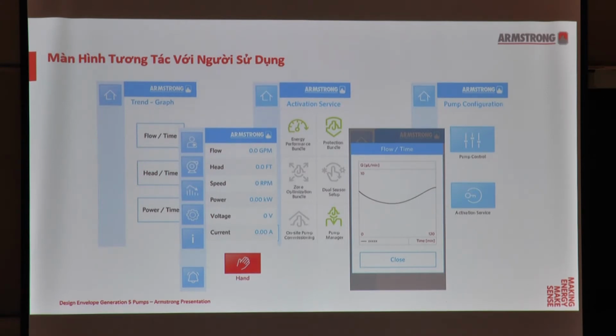Okay, here shows the interface of the DEPC card. Like this shows we can see the trend graphs and also some parameters, the flow, head, speed, and power, voltage, current, and so on. And all of these units can be set up. And for this activation service, we can activate some functions like the energy performance bundle and protection bundles. Like this protection bundle, it includes such as the minimum flow protection, the maximum flow protection, and also have the zone optimization bundle, dual season setup, and so on.